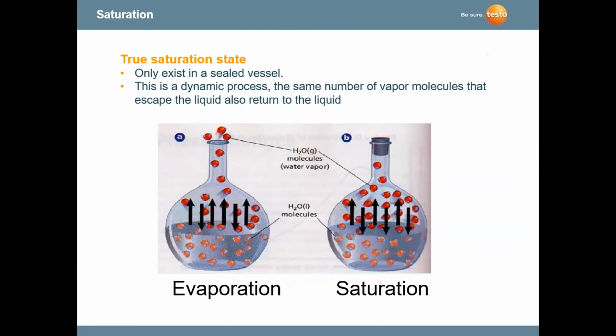Talking a little bit about pressures, going back to the previous slide we went through, when we add heat, we change from a liquid to a vapor. When we remove heat, we change from a vapor to a liquid. And we call that, in a sealed system, and that's what we have in an air conditioning system, saturation. On the far right beaker there, as you add heat, the liquid is changing to a vapor and then from a vapor back to a liquid. Nothing is being lost in the process as far as the refrigerant.